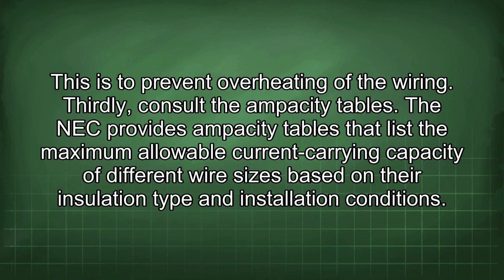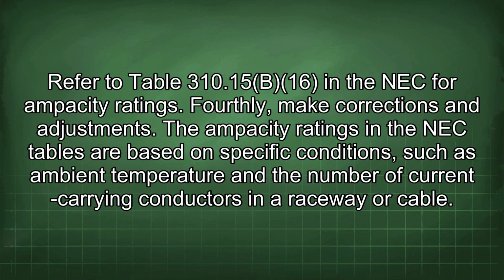Thirdly, consult the ampacity tables. The NEC provides ampacity tables that list the maximum allowable current carrying capacity of different wire sizes based on their insulation type and installation conditions. Refer to Table 310.15(B)(16) in the NEC for ampacity ratings.